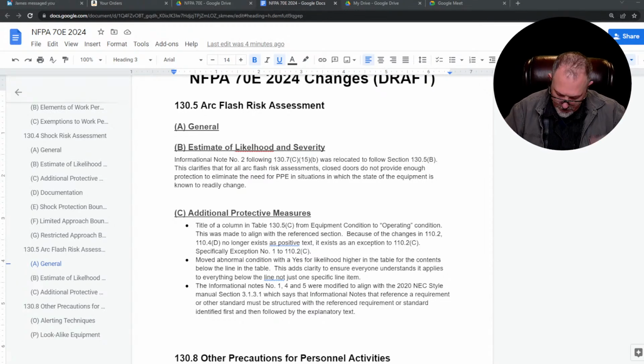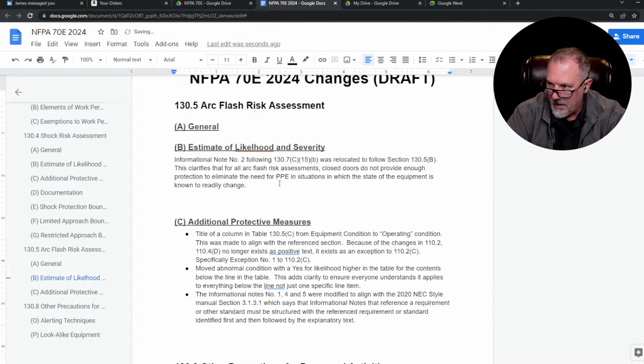So we go to table 130.5(C), estimate of the likelihood of occurrence of an arc flash incident. And it says operation of a circuit breaker, switch, contactor, or starter in normal equipment condition, there's no likelihood of an occurrence of an arc flash event. Now, this informational note says, in most cases, closed doors do not provide enough protection to eliminate the need for PPE in situations in which the state of the equipment is known to readily change. Oh, okay. Doors open or closed, racked in or out. Readily changing.